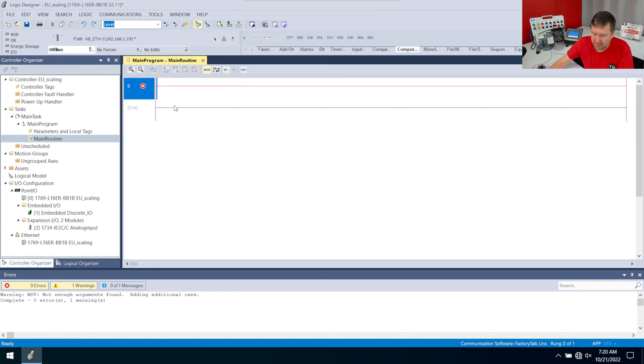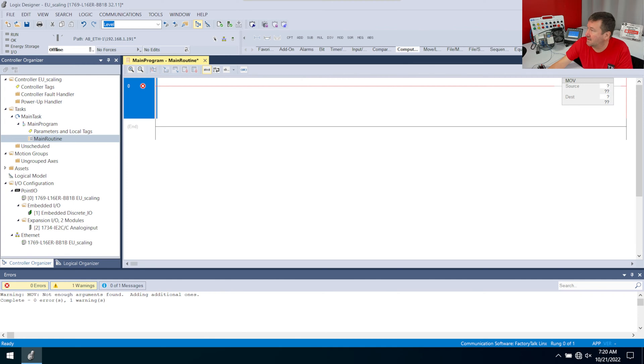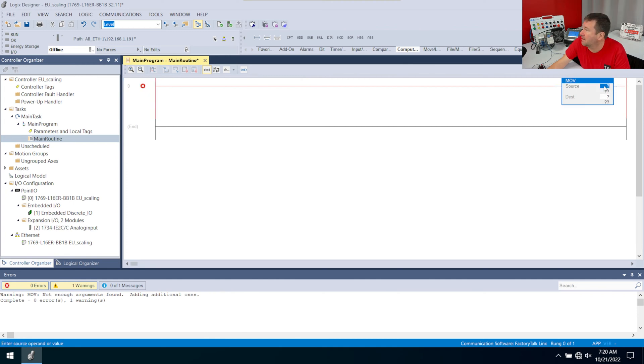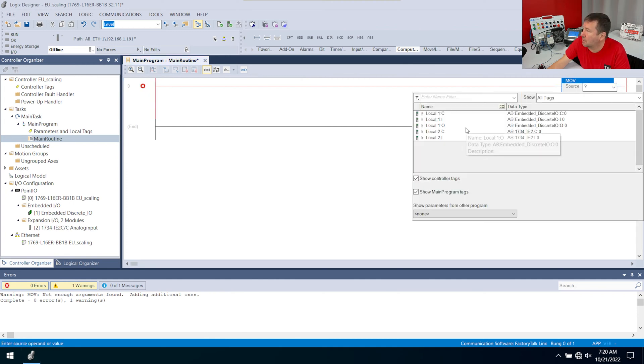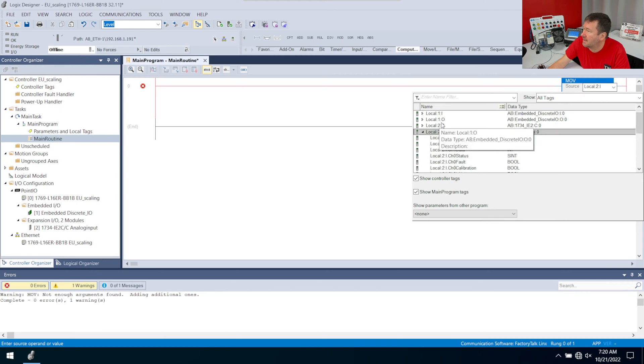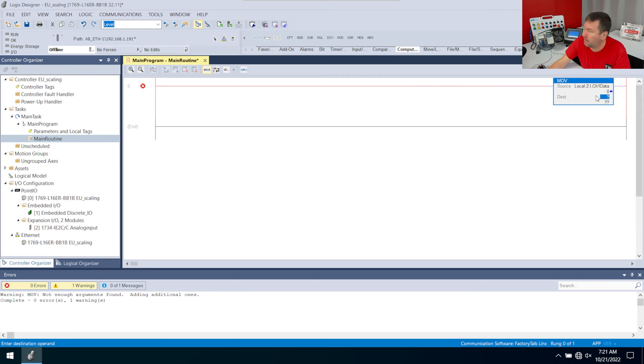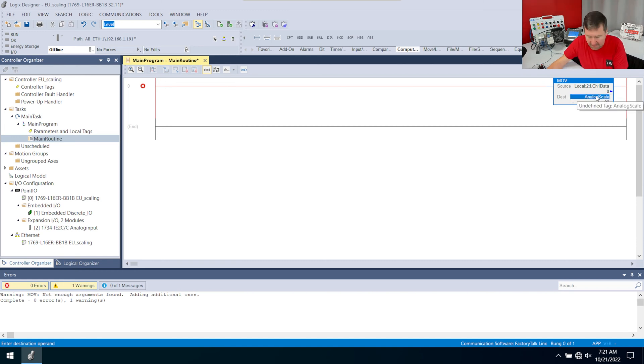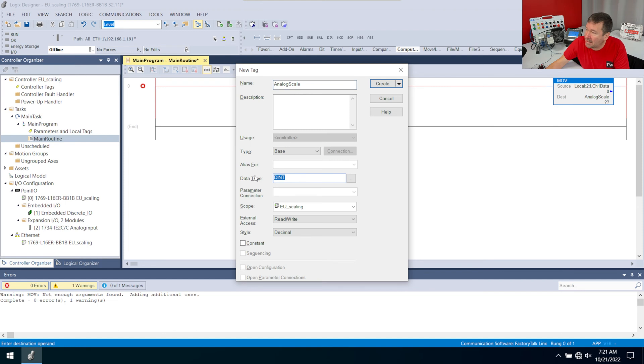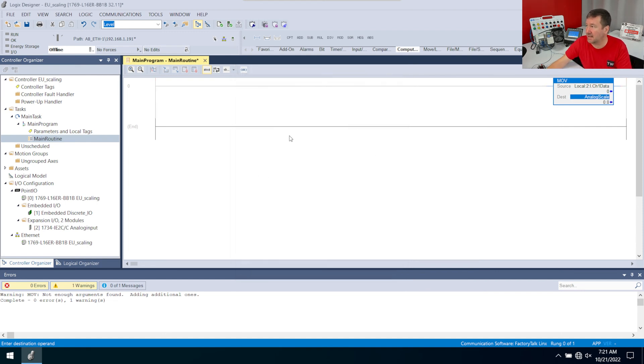Then I'm going to open up my main routine, and I'm going to bring a Move instruction down — this is just so we can see it on the HMI. Then I'm going to grab local colon 2 colon I CH1 data, and I'm going to put it in analog scale, because I already have that set up on the HMI, and I'm going to make this a real decimal, because we want a decimal in it. And I'm going to download this program.